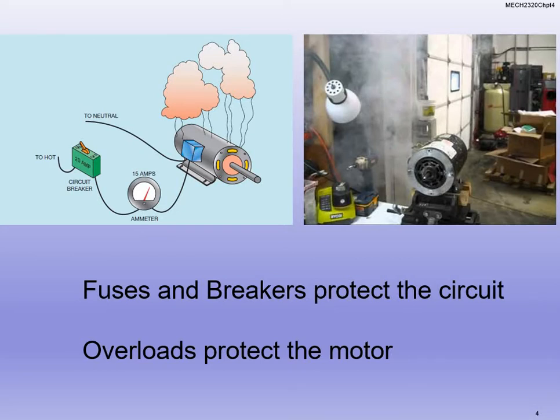So fuses, one shot. Breakers, we can use them over and over and over again, but they're protecting against the inrush of current. So you're protecting the equipment that's being plugged in, essentially, because if it draws too much current, you can burn up the motors. That's really essentially what's going on. With fuses, we're protecting all of our electronics from frying and overloading. And then we're going to talk about overloads. That's another way we protect the motor.